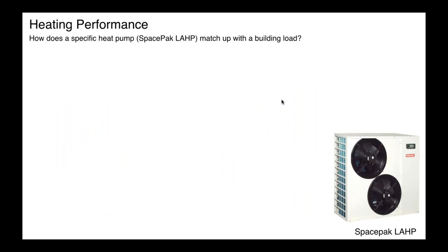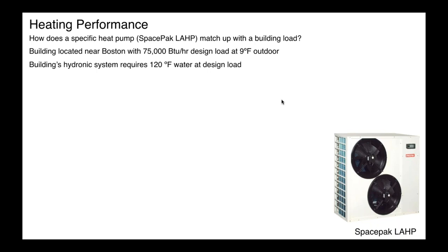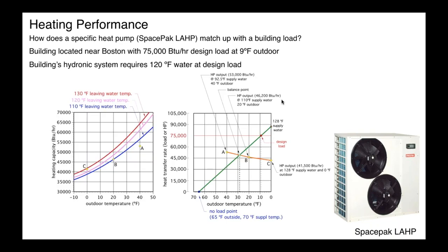Okay, so again, how does a specific heat pump, in this case, we're modeling a SpacePak, what they refer to as a low ambient heat pump. It's a nominal 4-ton monobloc style system. It has the enhanced vapor injection in it. How does it match up with that specific load? So this house in Boston that we set the spreadsheet up around was a 75,000 BTU per hour design load, 9 degree outdoor temperature. As I just mentioned, building hydronic system requires 120 degree water at design load.